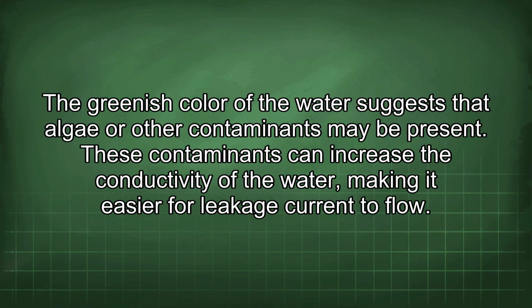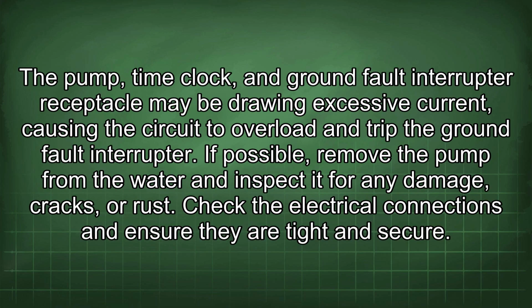The greenish color of the water suggests that algae or other contaminants may be present. These contaminants can increase the conductivity of the water, making it easier for leakage current to flow. The pump time clock and ground fault interrupter receptacle may be drawing excessive current, causing the circuit to overload and trip the ground fault interrupter.